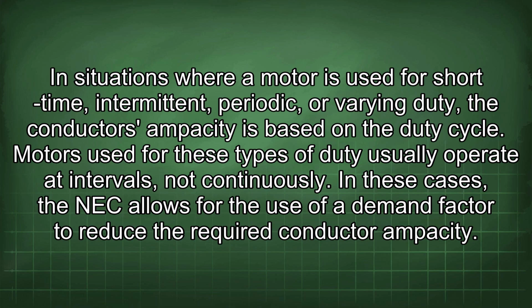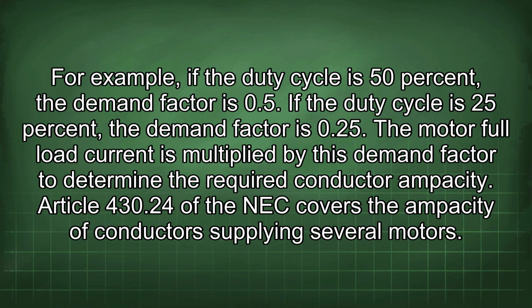In situations where a motor is used for short time, intermittent, periodic, or varying duty, the conductor's ampacity is based on the duty cycle. Motors used for these types of duty usually operate at intervals, not continuously. In these cases, the NEC allows for the use of a demand factor to reduce the required conductor ampacity. For example, if the duty cycle is 50%, the demand factor is 0.5. If the duty cycle is 25%, the demand factor is 0.25. The motor full load current is multiplied by this demand factor to determine the required conductor ampacity. Article 430.24 of the NEC covers the ampacity of conductors supplying several motors.